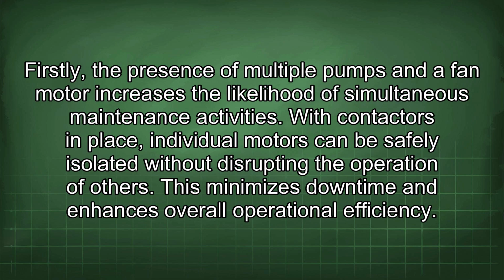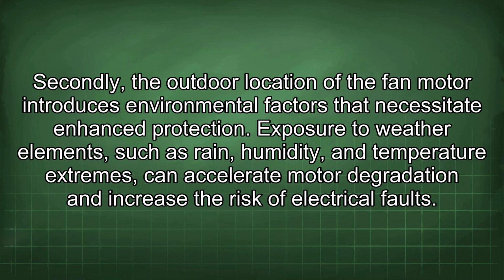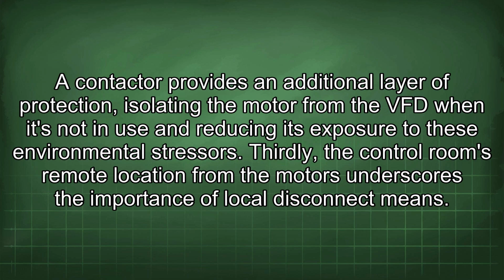With contactors in place, individual motors can be safely isolated without disrupting the operation of others. This minimizes downtime and enhances overall operational efficiency. Secondly, the outdoor location of the fan motor introduces environmental factors that necessitate enhanced protection. Exposure to weather elements such as rain, humidity, and temperature extremes can accelerate motor degradation and increase the risk of electrical faults. A contactor provides an additional layer of protection, isolating the motor from the VFD when it's not in use and reducing its exposure to these environmental stresses.